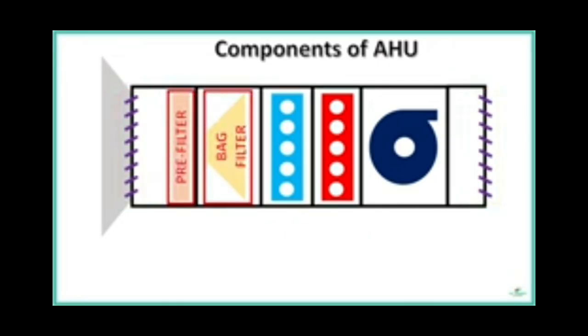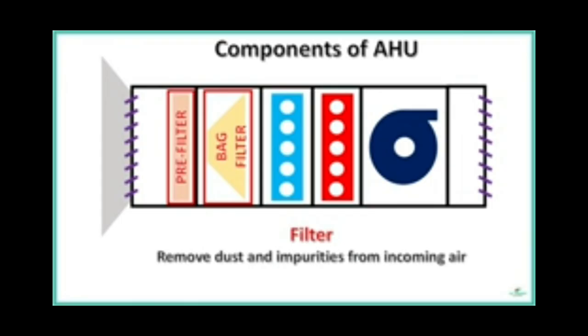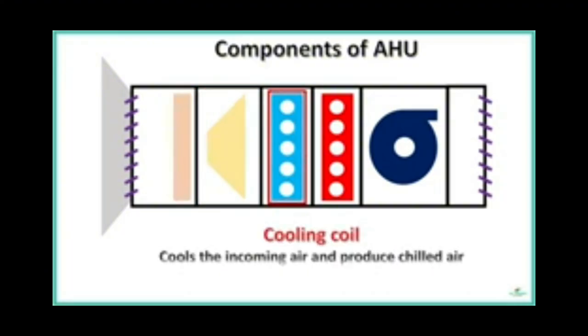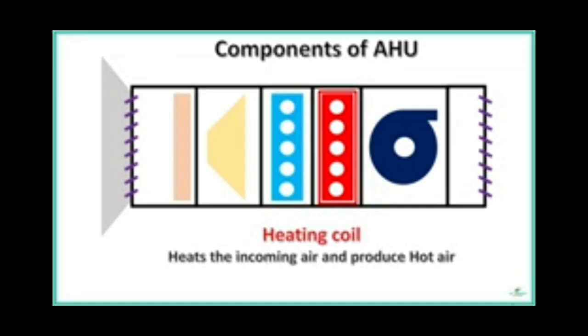Once the air enters the AHU, it is filtered to remove dust particles and impurities by 2 stages of filters. Now the filtered air enters the important component of an AHU, a cooling coil. A cooling coil converts the filtered atmospheric air into clean chilled air, which cools the environment. Or it is passed through a heating coil that converts the filtered atmospheric air into clean hot air, which heats the environment.